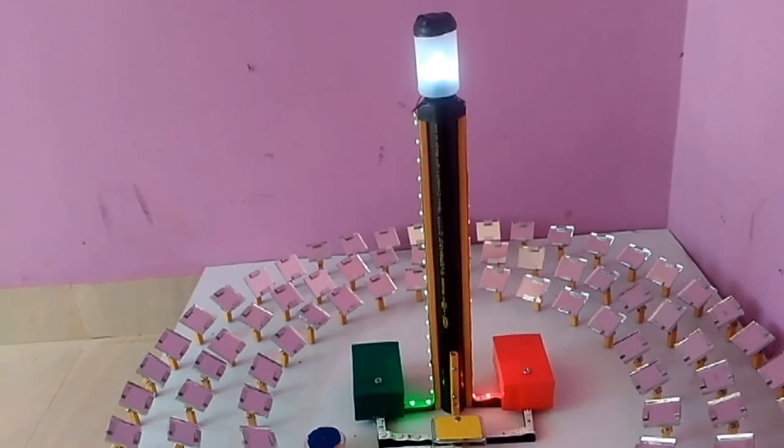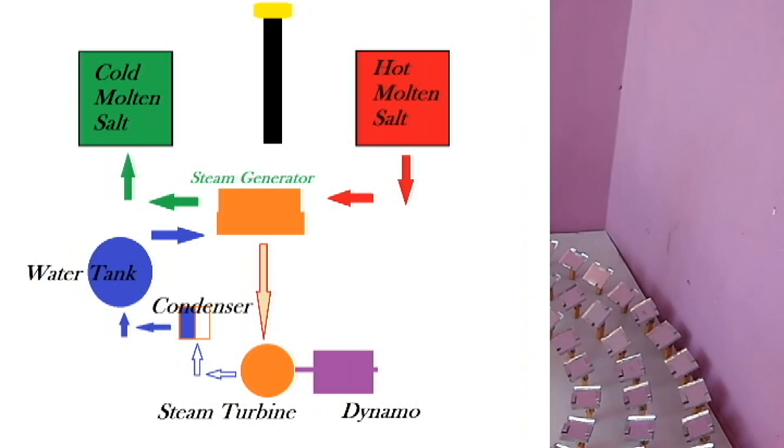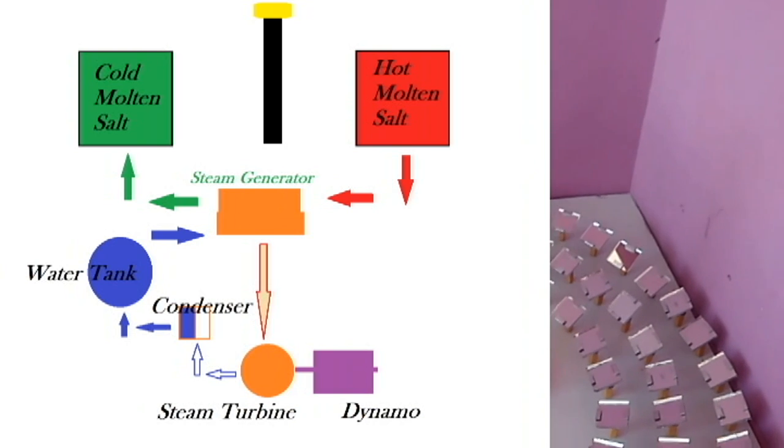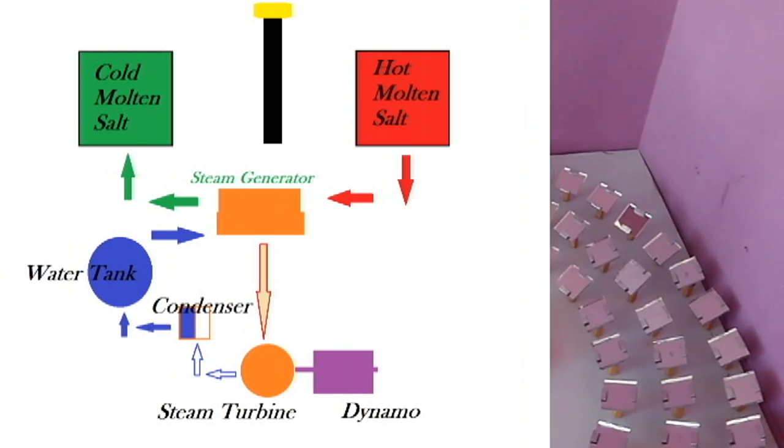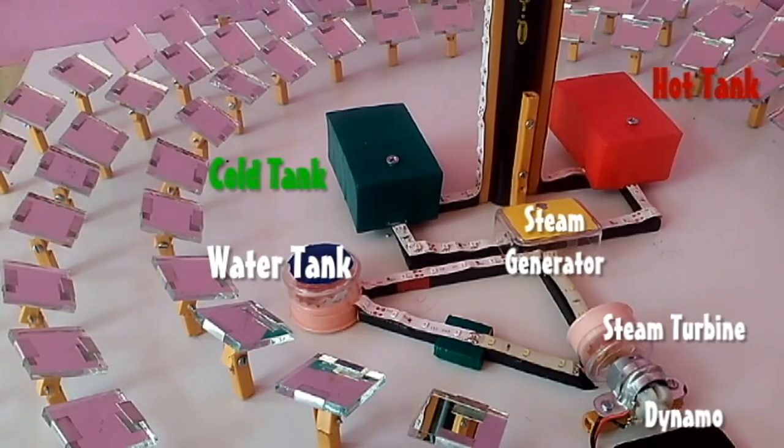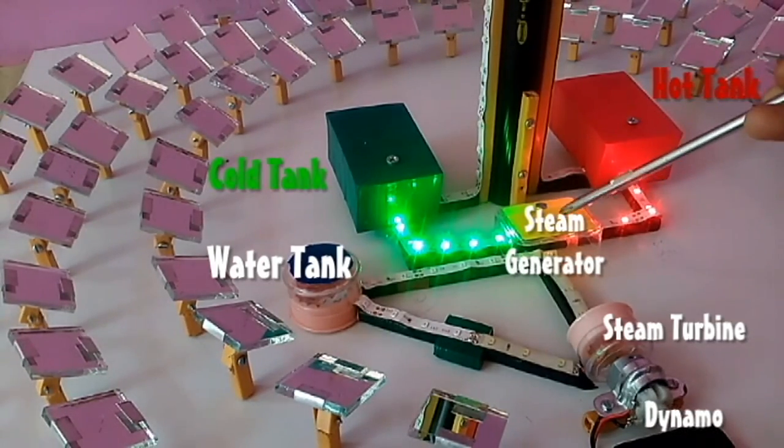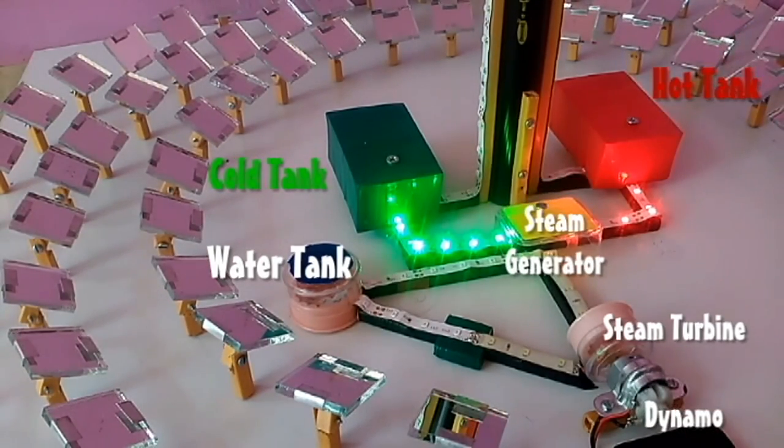This technology leverages liquid molten salt as both the energy collection and the storage mechanism, which allows it to separate energy collection from electricity generation. When electricity is required by the utility, day or night, the high temperature molten salt flows from the thermal storage tank to the steam generator as water is piped in from the water storage tank to generate steam.